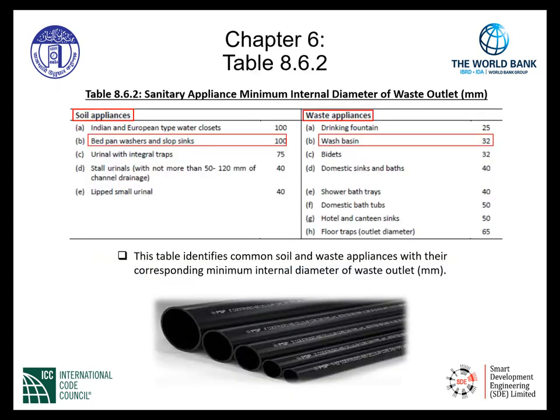Referencing Table 8.6.2 — sanitary appliance minimum internal diameter of waste outlet — soil appliances such as bedpan washers and slop sinks require a minimum internal diameter of 100 mm. Waste appliances such as a wash basin must have a minimum internal diameter of 32 mm.